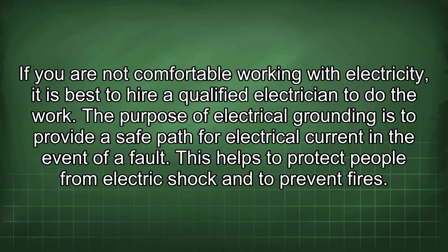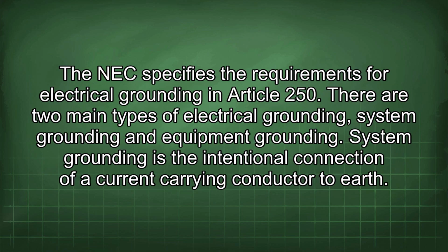The purpose of electrical grounding is to provide a safe path for electrical current in the event of a fault. This helps to protect people from electric shock and to prevent fires. The NEC specifies the requirements for electrical grounding in Article 250. There are two main types of electrical grounding: system grounding and equipment grounding. System grounding is the intentional connection of a current-carrying conductor to earth.